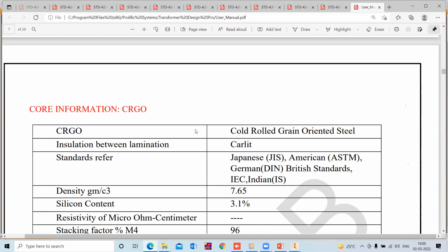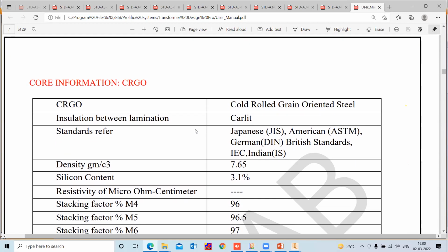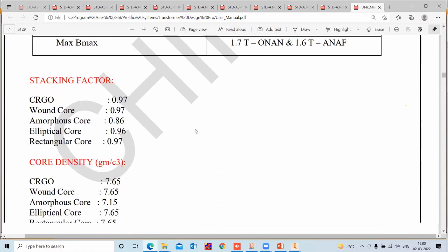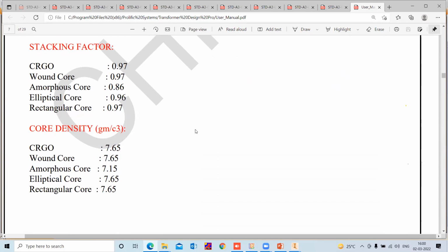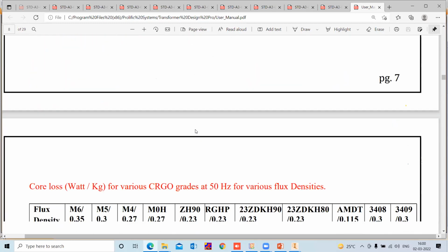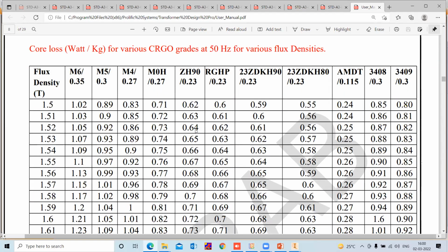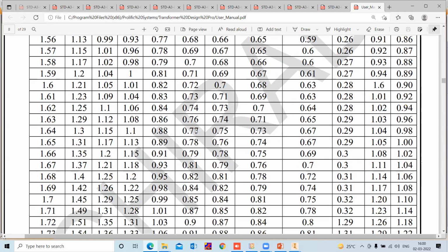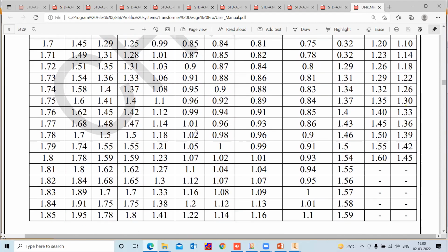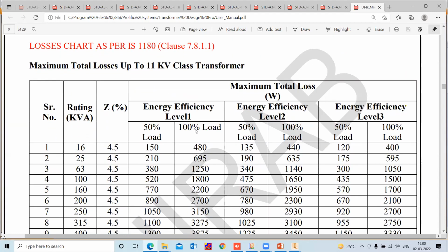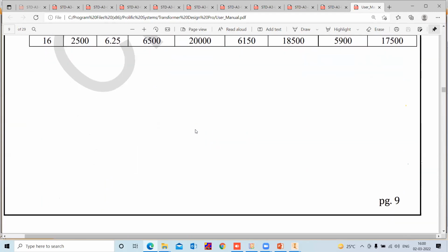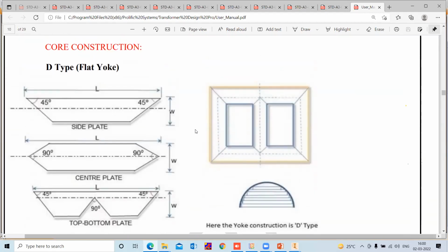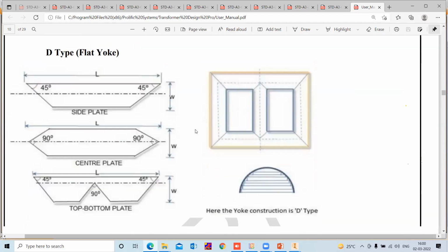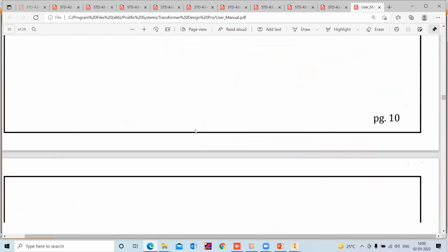Then the insulation grade, CRGO insulation grade, then the stacking factors for different kinds of cores, core densities for weight calculation. You can see the core chart, watt per kg chart with the grades. Then the losses chart as per IS 1180 with the impedance and kVA rating and the losses. Now you can see the core type. Software has multiple options like D-type flat yoke. So what are the differences? The differences you'll get in these diagrams in the PDF, like wound core, shell core, amorphous core.